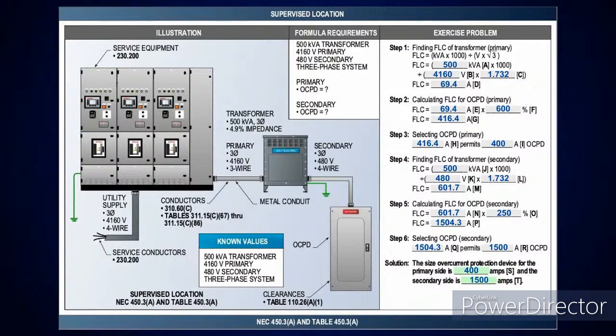Now, look at this. The exact same one we just did, but I'm in a supervised location. The impedance is still 4.9%. Now, if I come down and look in table 450.3A at not more than 6%, you're going to see 600%, but I want to point something out. See where there's no superscript 1 right there? This means you're going to drop down because I'm above that 125%.